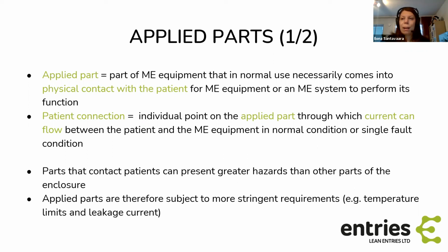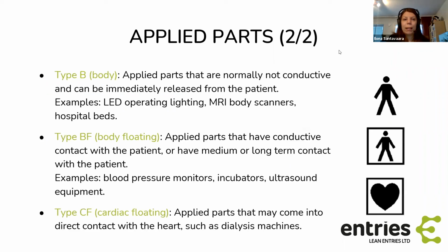And why these are handled separately is because parts that contact patients can present greater hazards than other parts of the enclosure. So of course the biocompatibility that we discussed in the first part of the presentation is one of those hazards that they may present, but there are others as well, related to electrical safety or electric shock hazards, for example. So they are subject to stricter requirements like temperature limits, leakage current. And then the types of applied parts are B, BF, and CF, and they are identified by these icons on the labeling on the right.